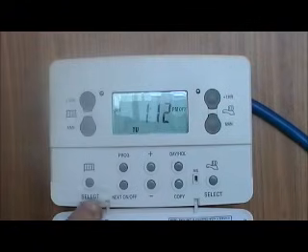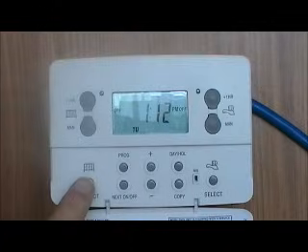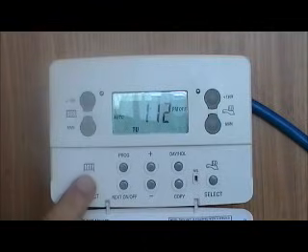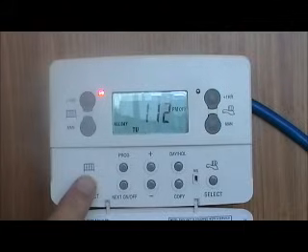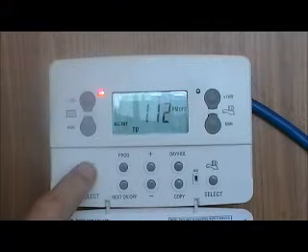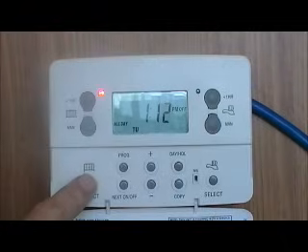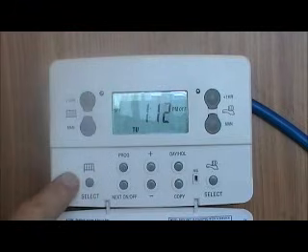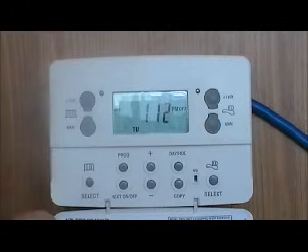By pressing the select button you can set the heating or the hot water to come on according to the timed program, which is auto, to be on all day. This turns the heating on at the earliest program's on time and off at the latest program's off time. And you see the red lights come on just to indicate that it's telling the boiler to fire. You can also, pressing select again, have it on all of the time or off all of the time. For example, during the summer you might want to just turn the boiler off for the central heating.